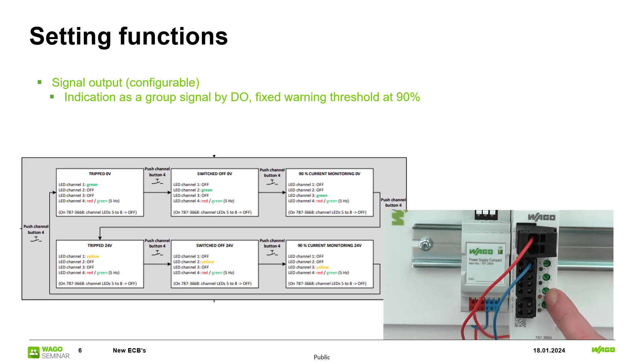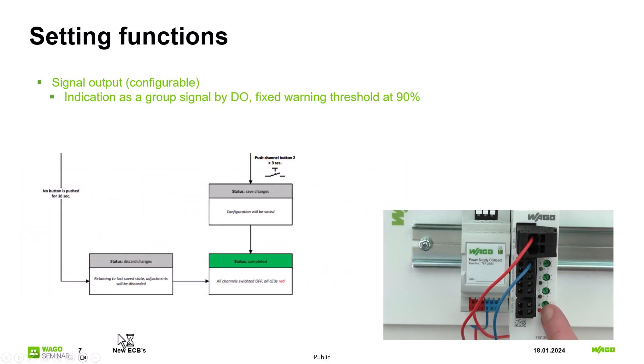And if the channel number 3 lights up orange you can use the warning threshold by 90%. If you do nothing for 30 seconds the configuration mode is automatically ended without saving. To save the settings simply press the button for channel number 2 again for more than 3 seconds. In both cases you must switch on the channels by yourself.